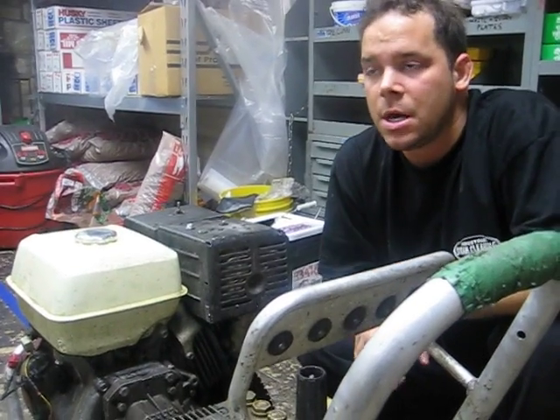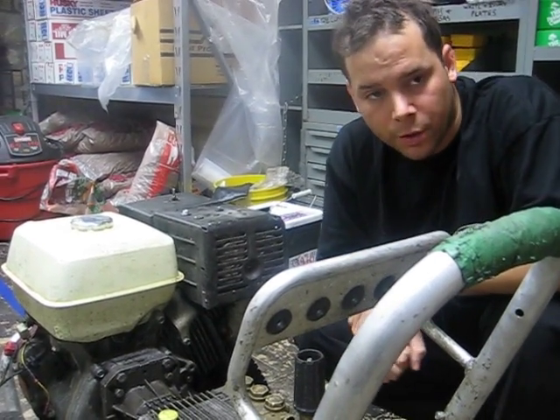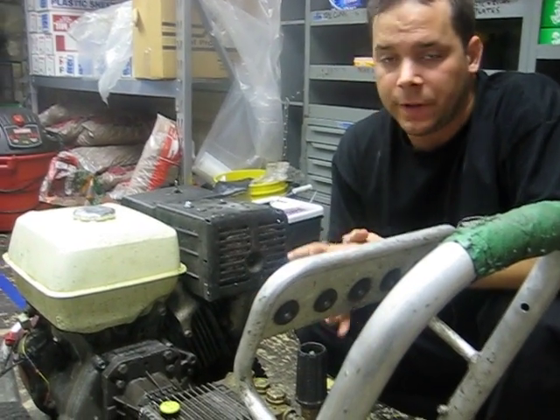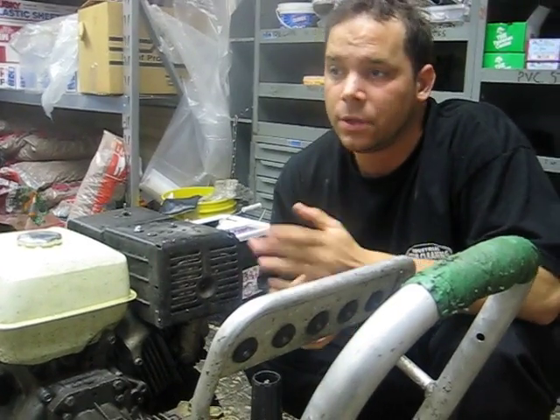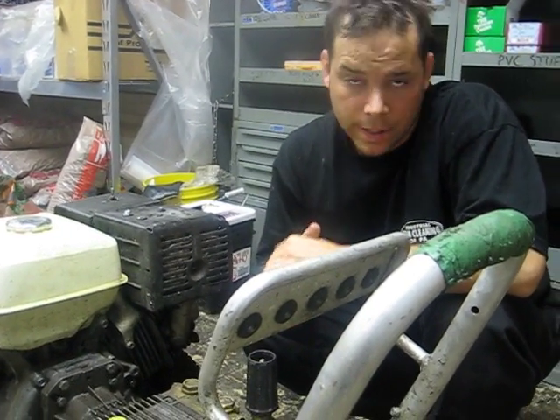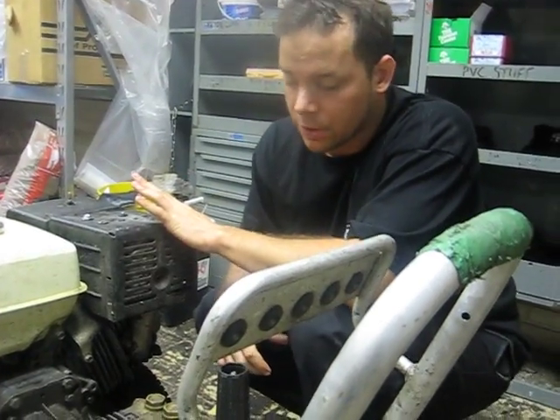And if that's all good and you're still having no pressure, you always use hot water when you're spraying the hoods, but if you still have no pressure, turn the cold water on as well and have hot and cold water on at the same time, and hopefully that will give you the pressure you need. If you do all that and you still have no pressure, then there's something wrong with the compressor, and then you call Greg.